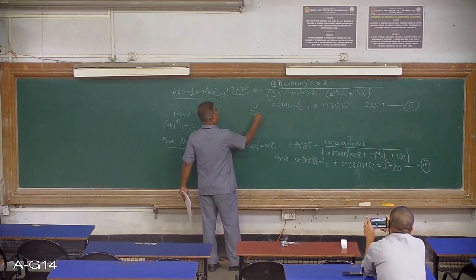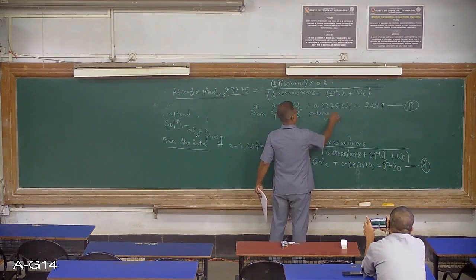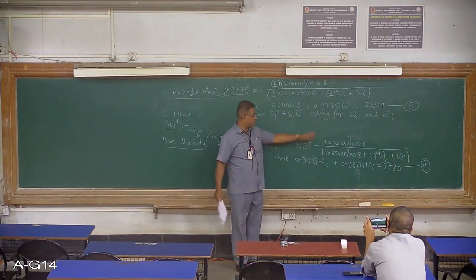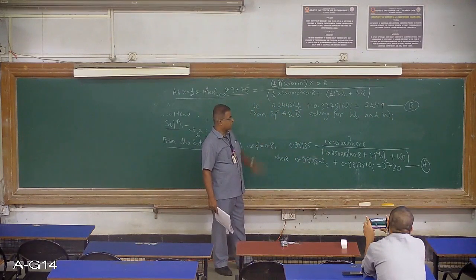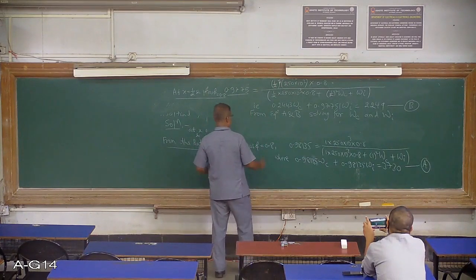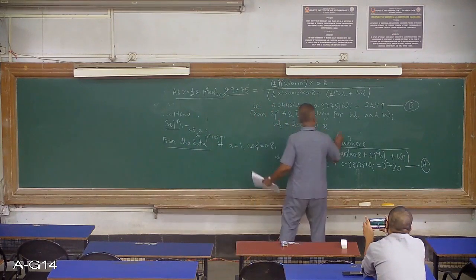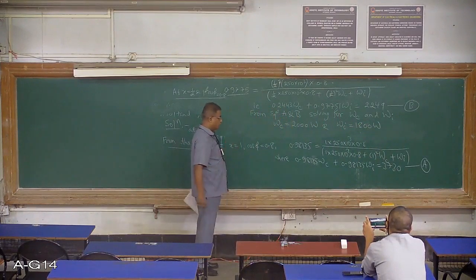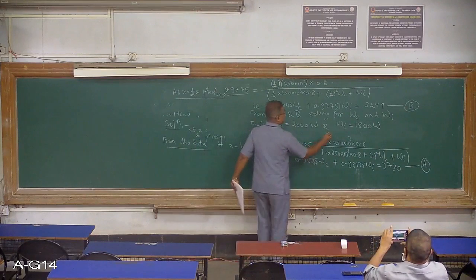From equations A and B, solving for WC and WI, you can use your calculator for solving these equations. Readily you will get the answer. So please look into the formalities to solve the equations A and B directly in your calculator. On doing that, you will get the answer readily as WC equal to 2000 watt and WI 1800 watt. So in this way, we have got the values of the full load copper loss, and this is iron loss.